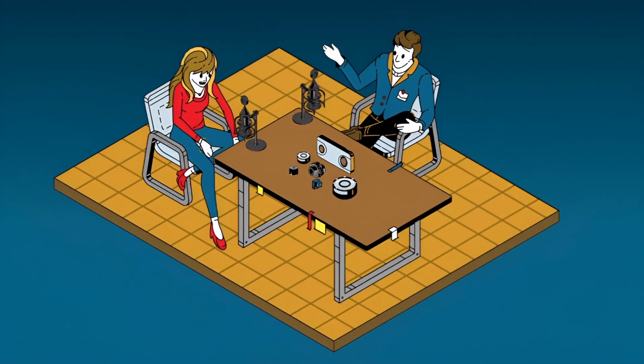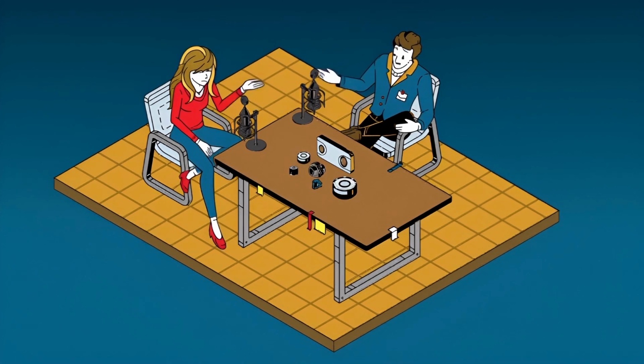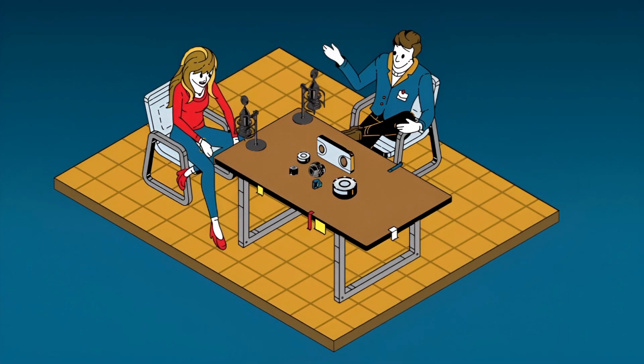Or hysteresis. Hysteresis, what's that? That's when you get a slightly different reading applying a load versus removing that same load. Calibration catches and corrects these things, keeping your data reliable. So it's like tuning up an instrument to make sure it's still playing the right notes accurately. Fighting that inevitable drift. That's a good way to put it.